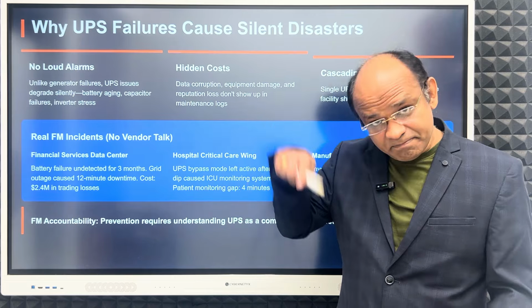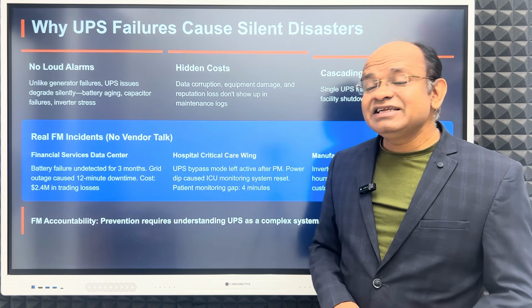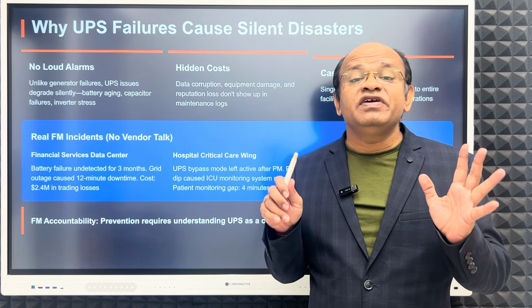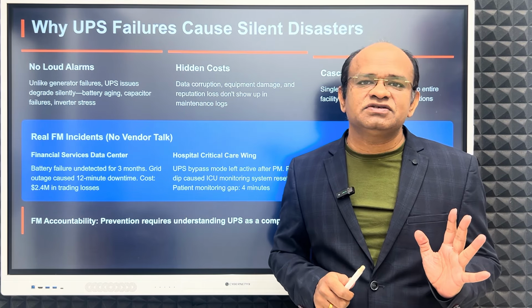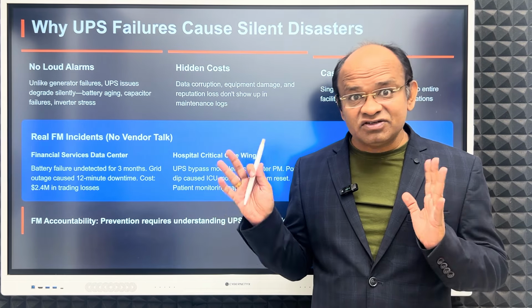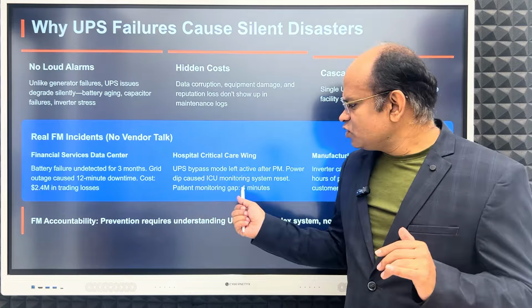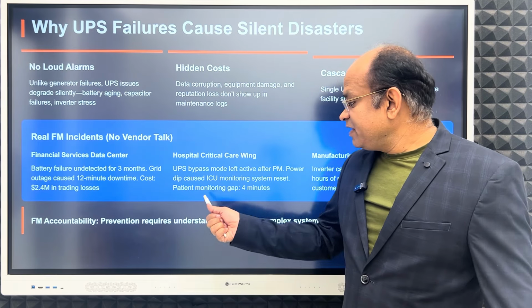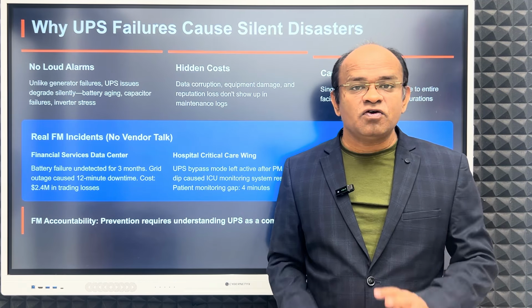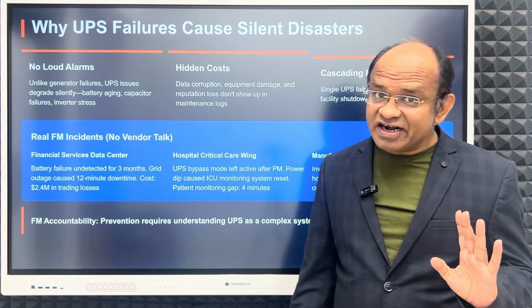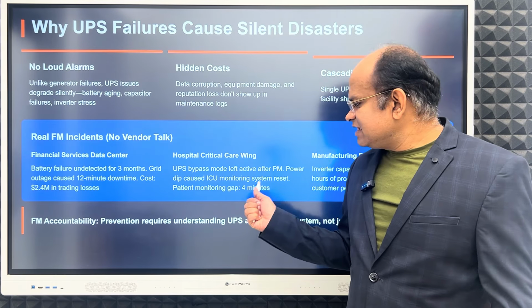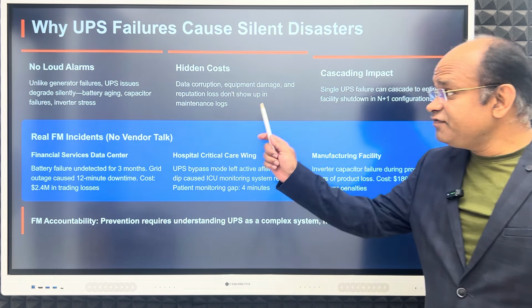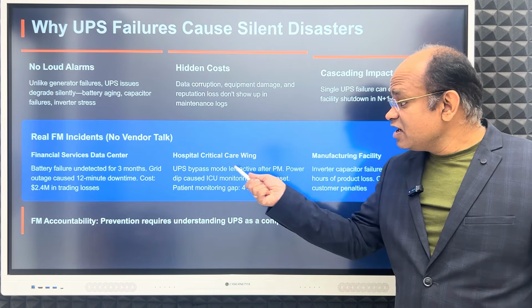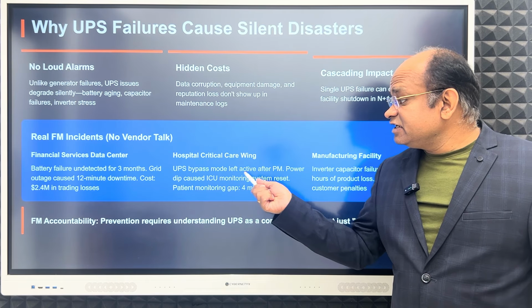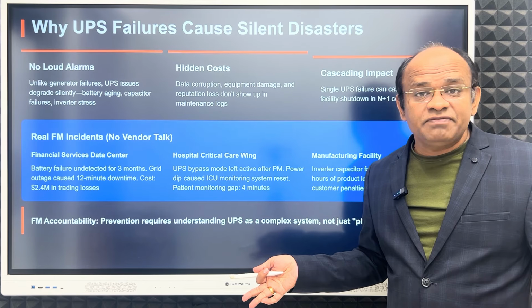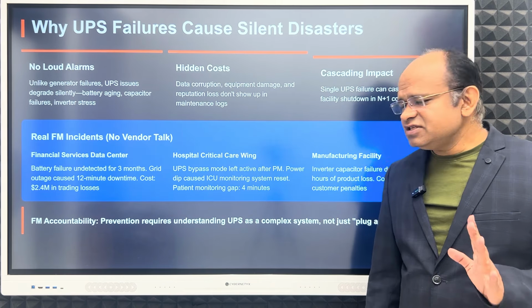Because of the power dip, the ICU monitoring system, which is very critical since lives depend on it, got reset. Patient monitoring was gapped for 4 minutes, they were not able to monitor patients. That's the problem if you don't have UPS properly activated, or if bypass mode is left active during preventive maintenance.